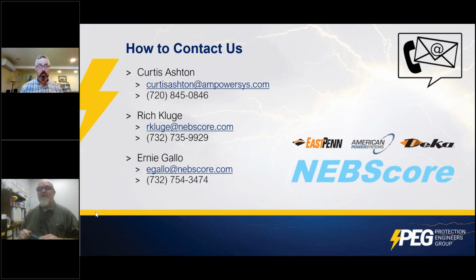Question 7. Regarding the NFPA 855, when you're referring to lithium ion, what about LFP? So lithium ion is a family of chemistries. Some are more dangerous than others, more likely to go into thermal runaway. And the questioner is correct that LFP is less likely to go into thermal runaway than most of the chemistries. LTO is even less likely than LFP. But basically, the way our money says, in God we trust, I like saying, in God we trust, all others must have data. That's the way the NFPA 855 committee looks at it. Bring us the data, and then we will make exemptions for LFP and LTO and things like that if you bring us enough data. So that's really where it's got to get to for different chemistries.